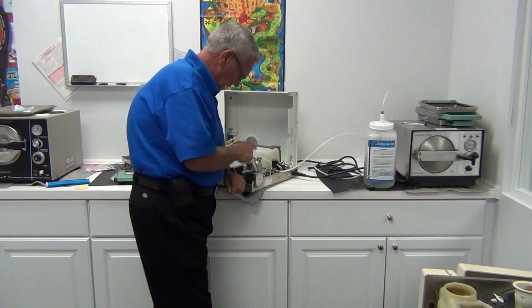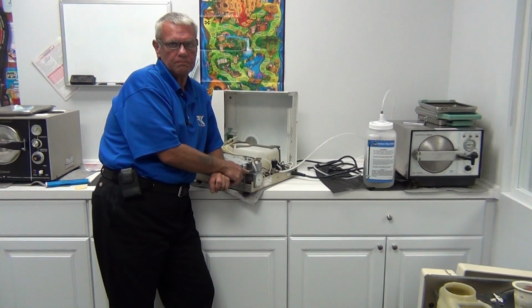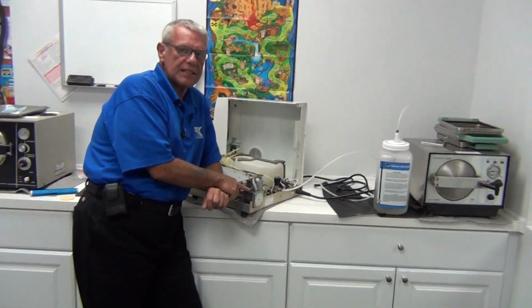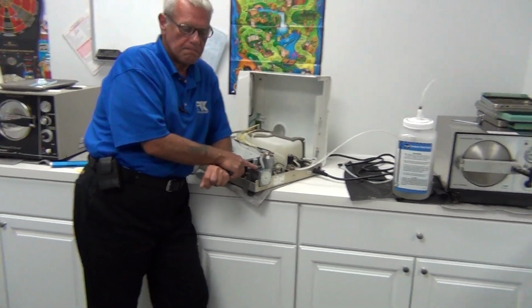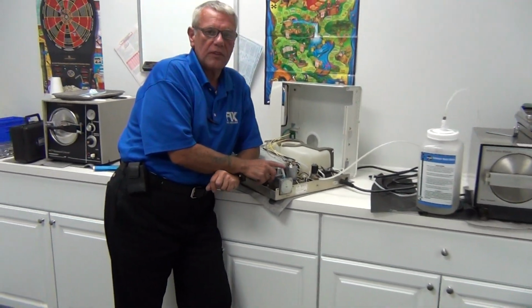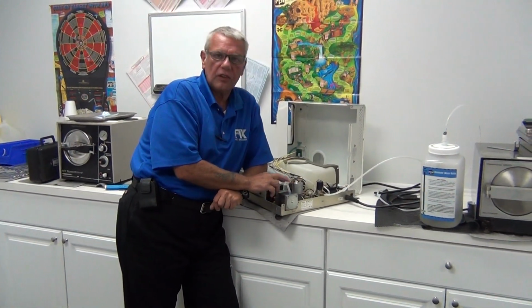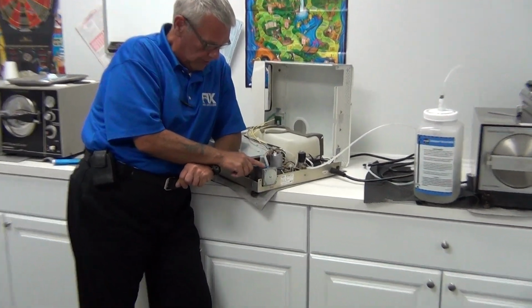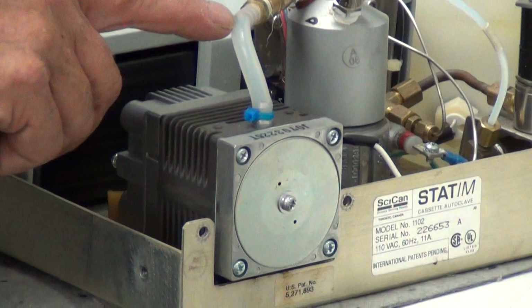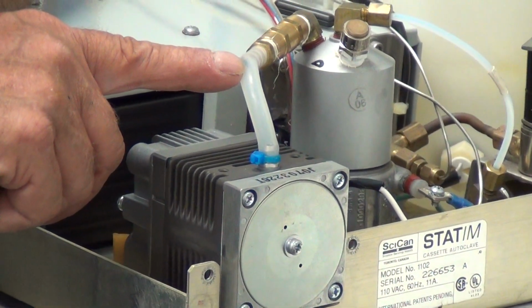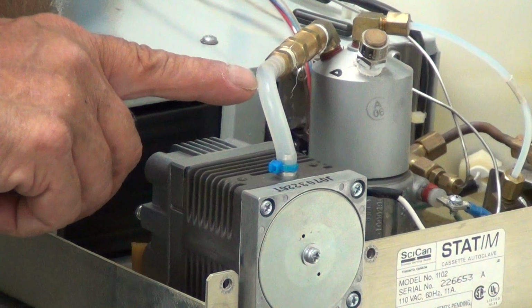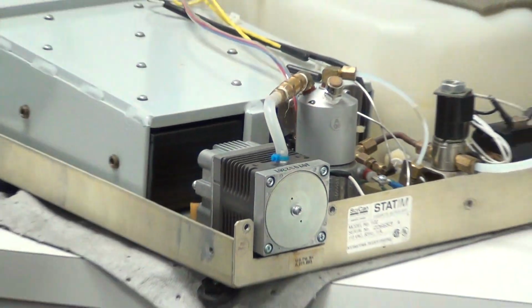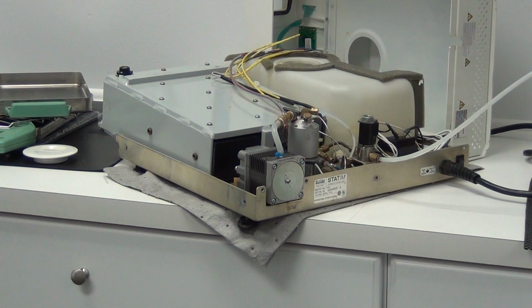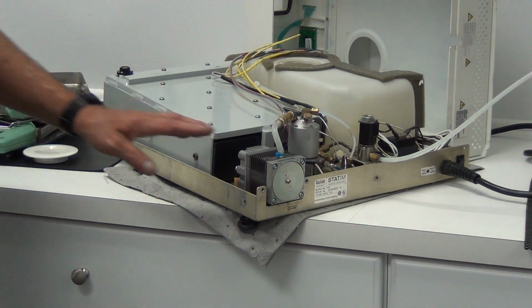Now, this is the air pump. This actually dries the instruments in the cassette. You can tell whether the air pump is original or factory by the color of the tubing. The original factory air pump will have a gray tubing. RPI has a clear tubing that you can actually see through, which is very, very good and very important, because without the clear tubing, you can't see if any water is getting into this.